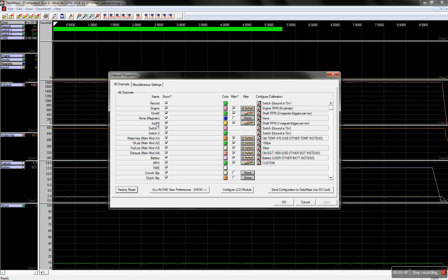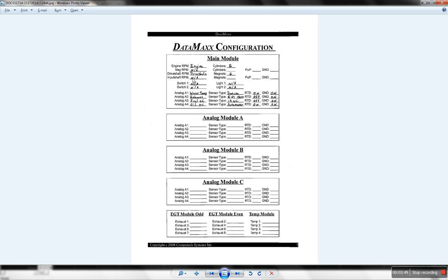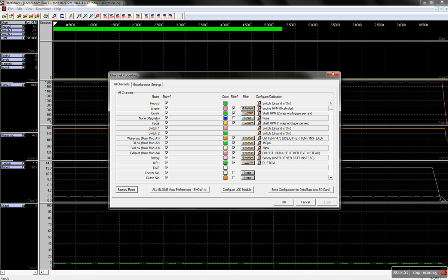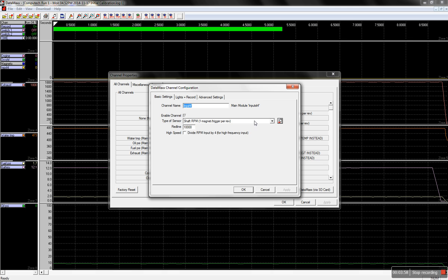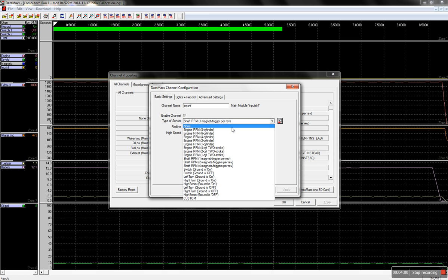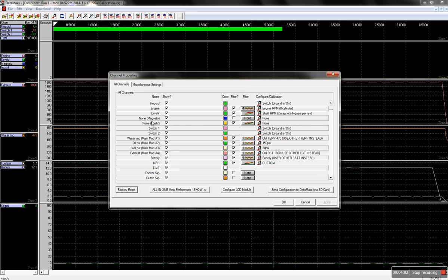Input shaft is the next line, and as you can see we are also not using input shaft, so we're going to disable that channel as well. Find input shaft, follow the line to the right, click on the calibration button. From the type of sensor drop-down list, go ahead and select none and hit OK. So now both of those channels have been disabled.